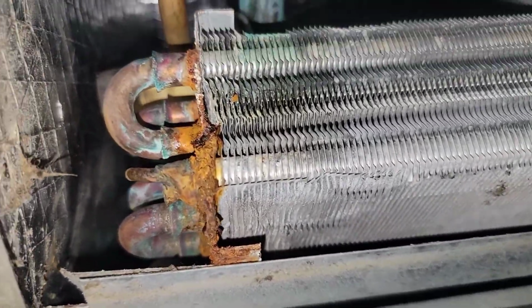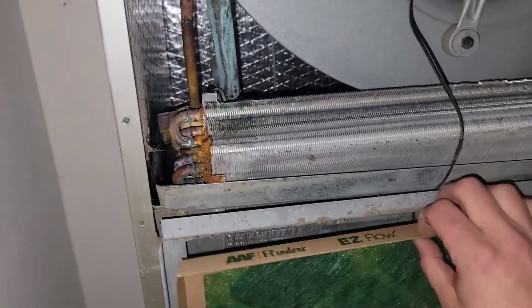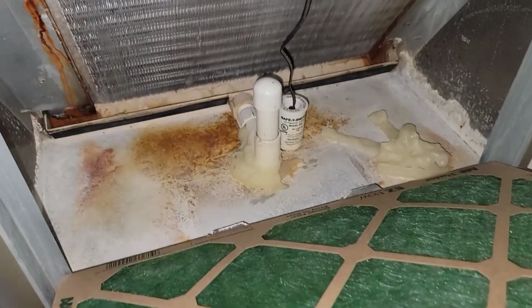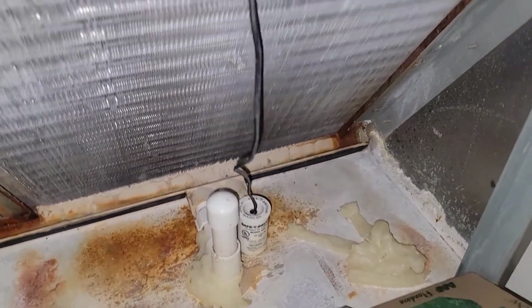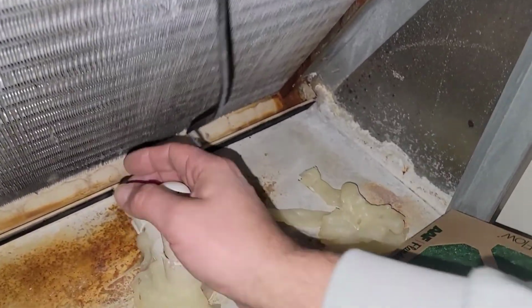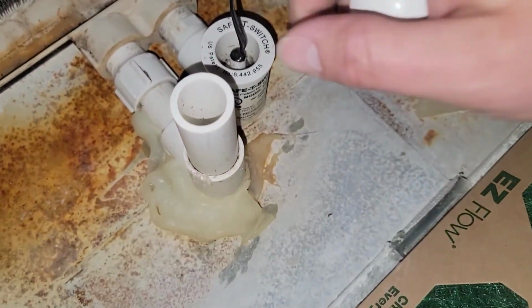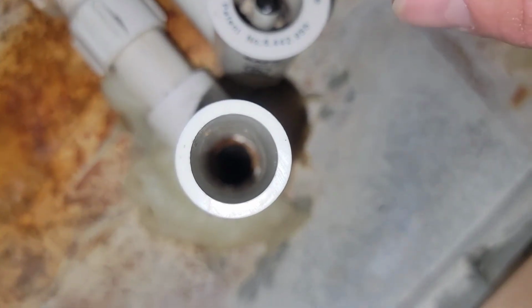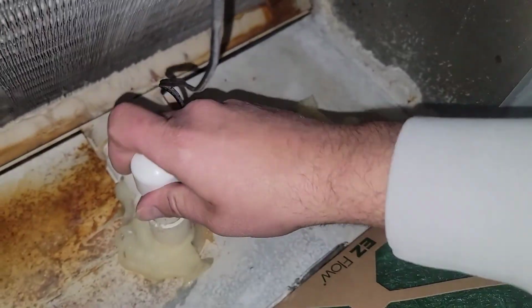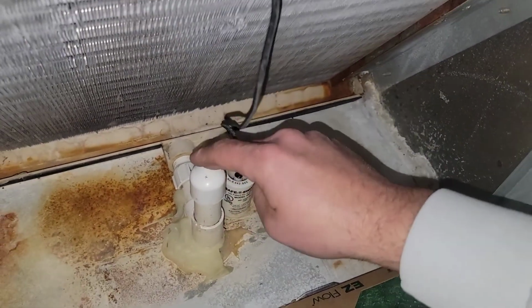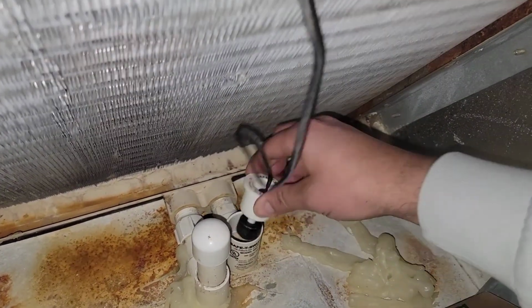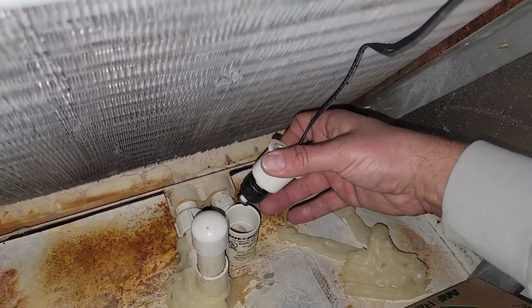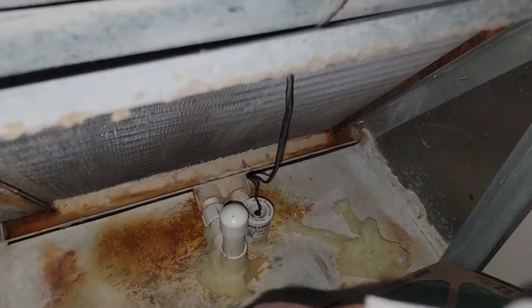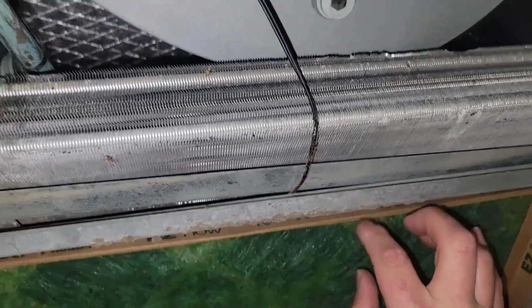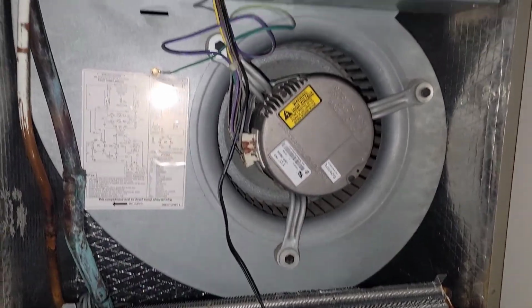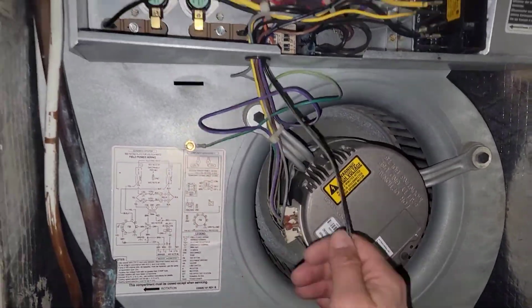You can tell we got some major rust, and I would not be surprised if this coil is leaking. Drains got to have good maintenance. Some of these apartments do not have good maintenance, and because of that, you will have these drains that are stopped up. You can put a shop vac on this, and this is a safety switch, a float switch, and when this float switch rises, it cuts the 24 volts power off. So if you ever have a blank thermostat because it doesn't have batteries, make sure you check the drain.